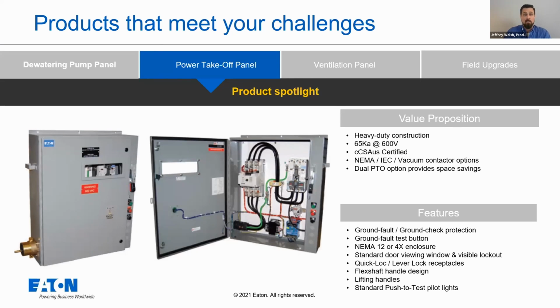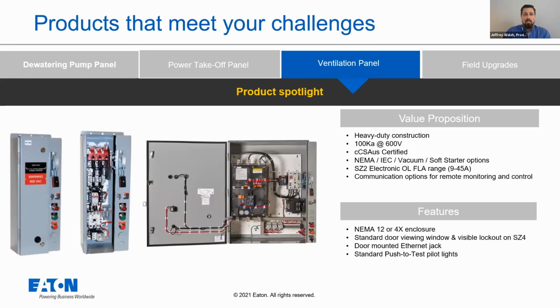So the benefits of a dual are a smaller footprint, rather than having two enclosures mounted side by side on a strut rack, and it only requires a single wire pull for the supply side. Now the vent panels are used for fan motors. And just like the pump panels, we offer across the line, so you can have the contactor and overload, or you can have a reduced voltage soft start option as well.